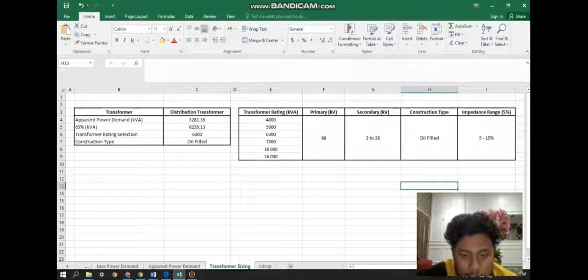Okay, so the total maximum demand of industrial loading must be less than or equal to 65% of the size of the full load transformer, since we see 6300 kVA is greater than 65% of the entire maximum demand of 6229.13 kVA. So the transformer rating for the discrete factory is 6300 kVA as stated in the table. Okay, it will alert the user if the transformer rating selected is lower than the predicted maximum demand and encourage the user to choose a higher transformer rating. Okay, like this.